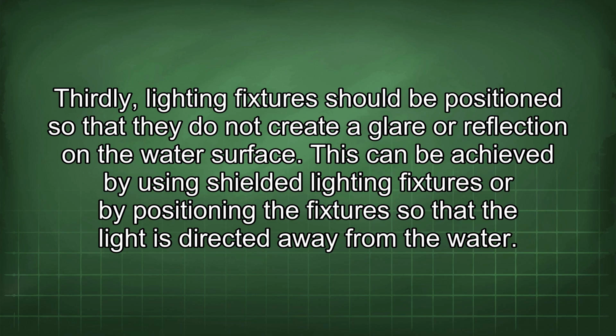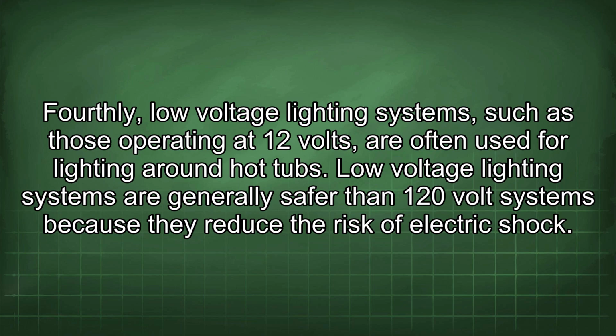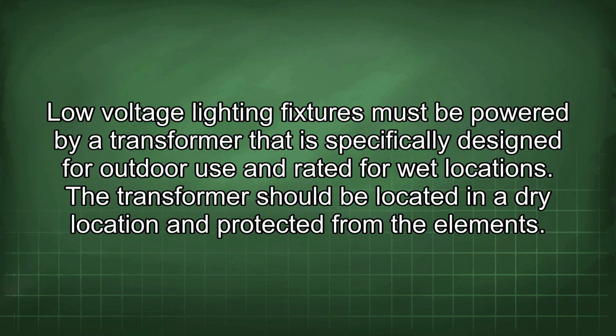away from the water. Fourthly, low-voltage lighting systems, such as those operating at 12 volts, are often used for lighting around hot tubs. Low-voltage lighting systems are generally safer than 120-volt systems because they reduce the risk of electric shock. Low-voltage lighting fixtures must be powered by a transformer that is specifically designed for outdoor use and rated for wet locations. The transformer should be located in a dry location and protected from the elements.